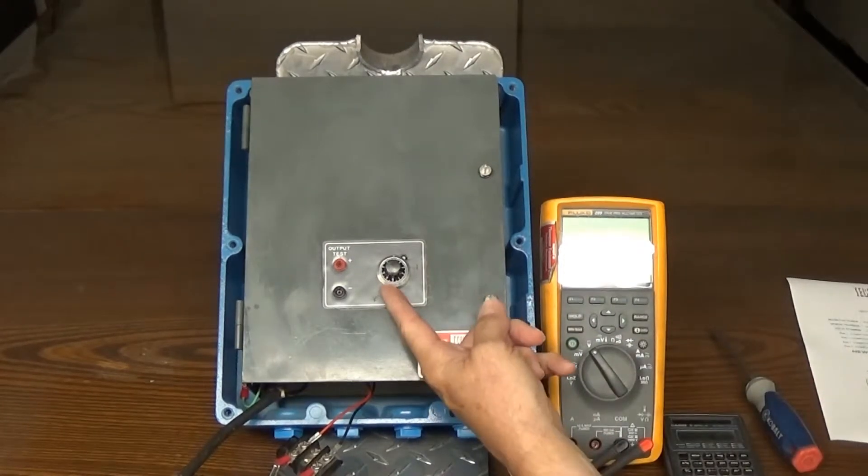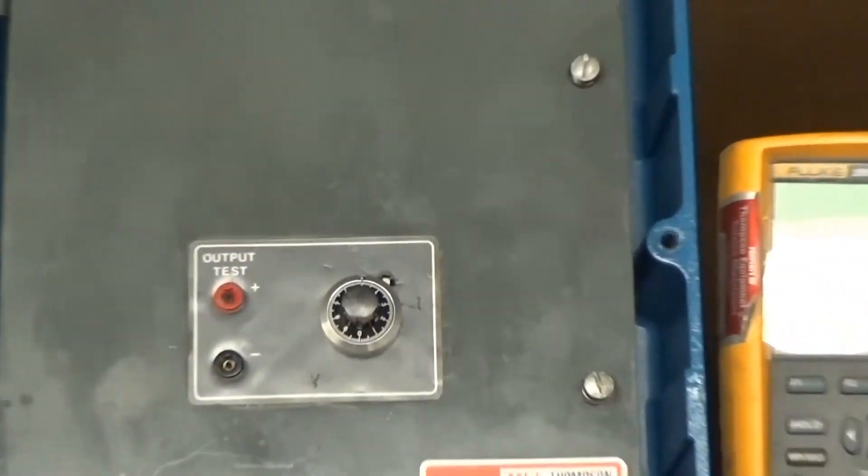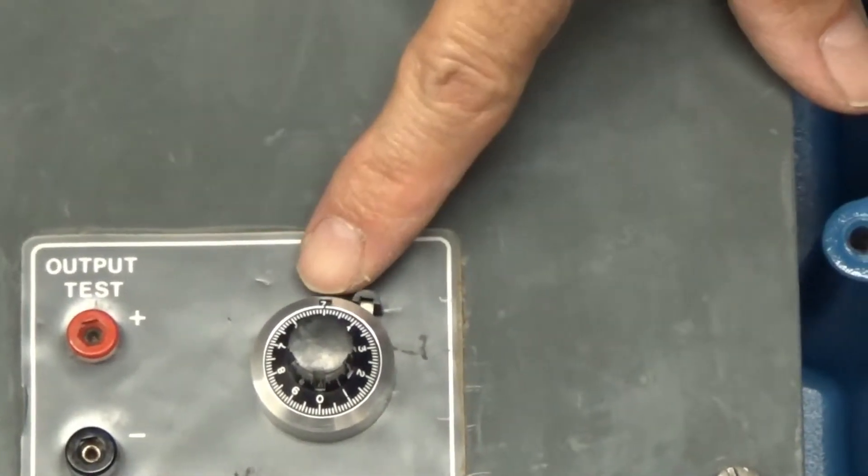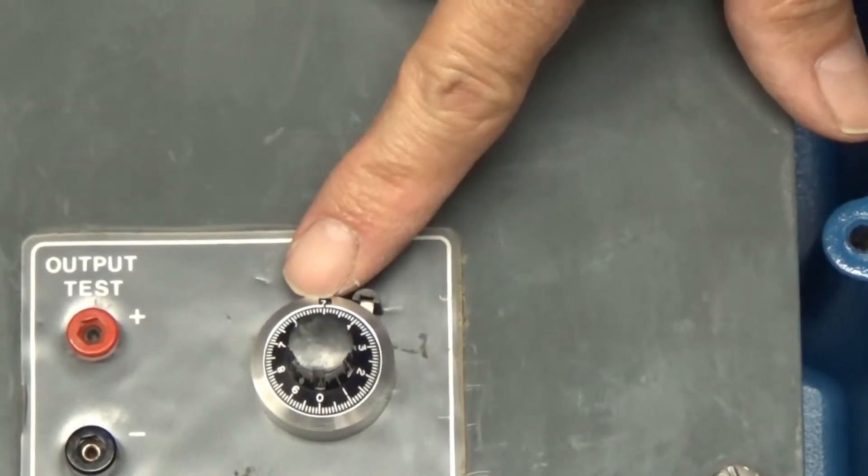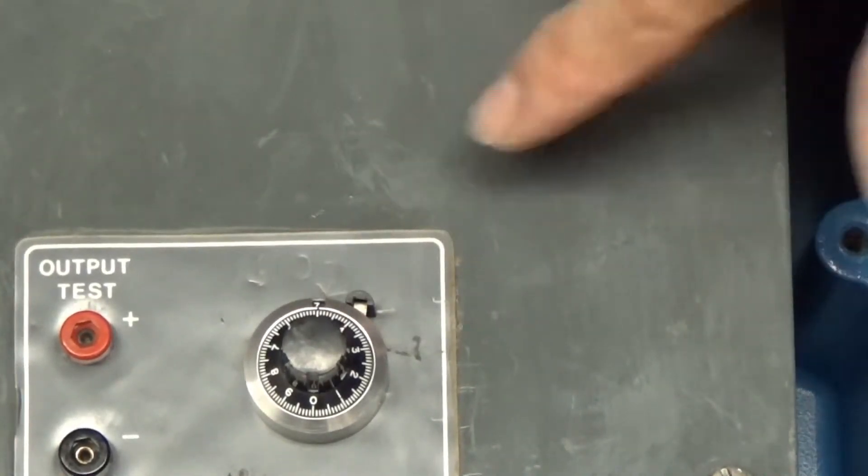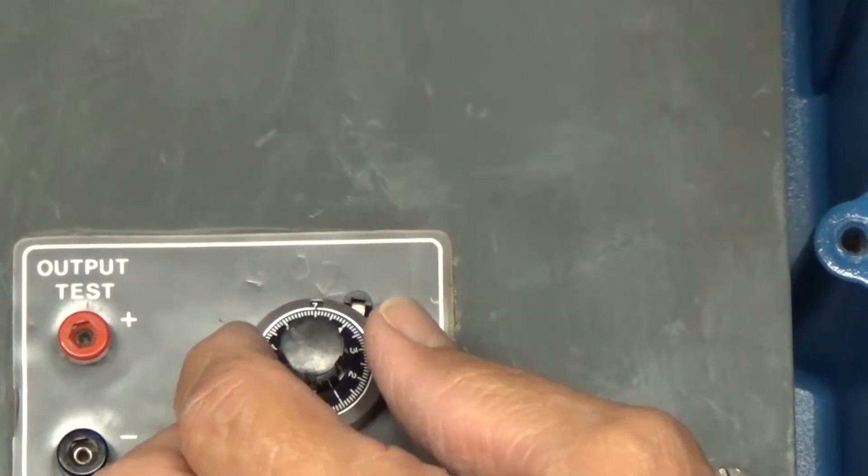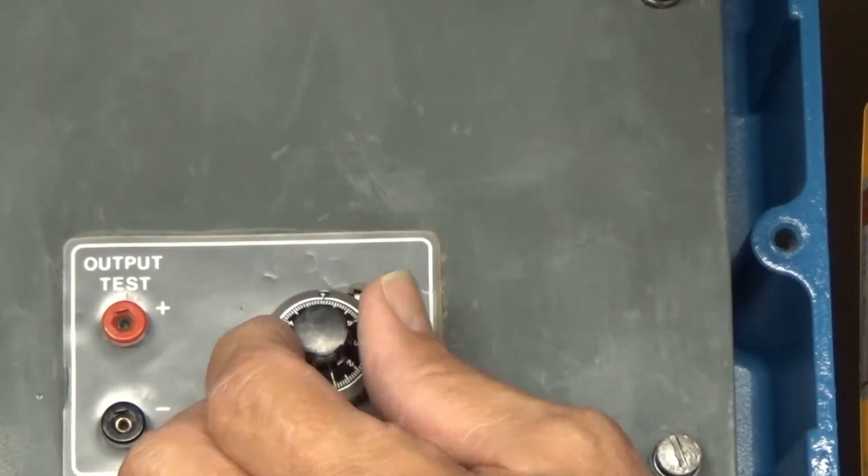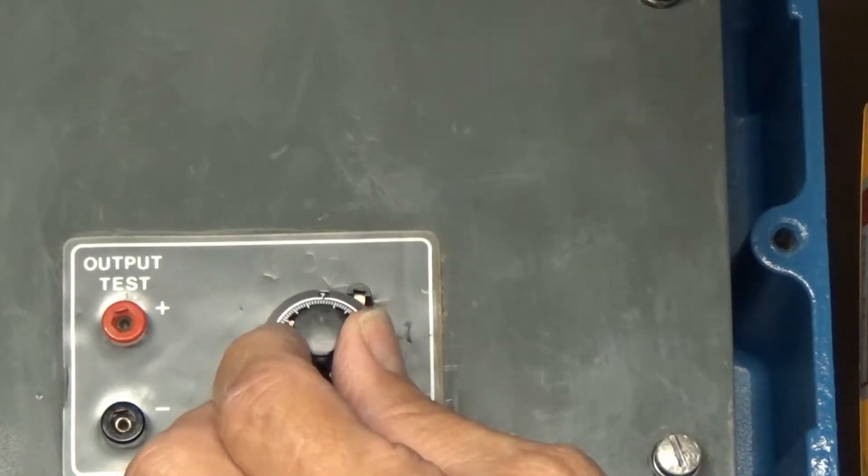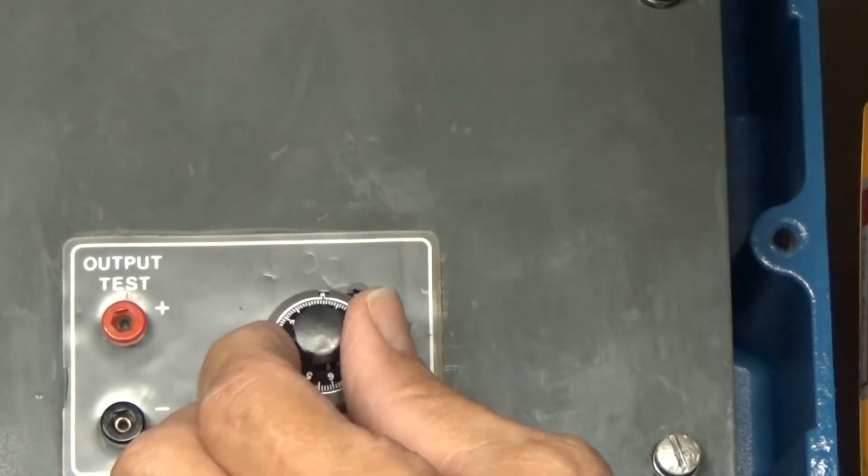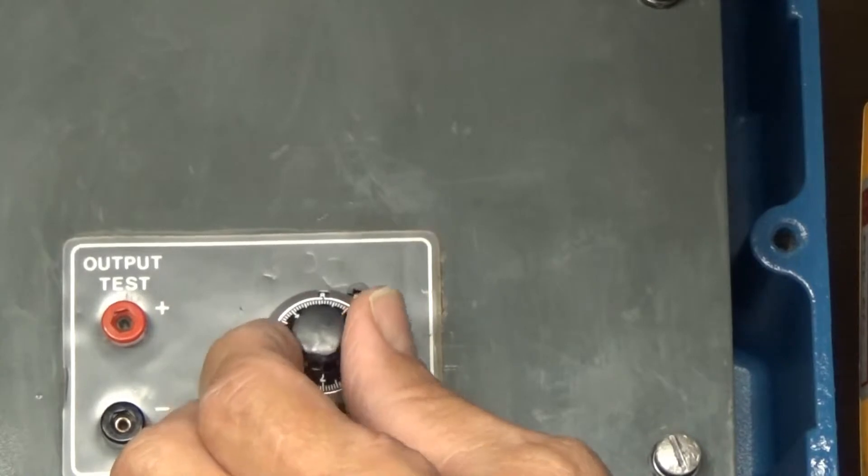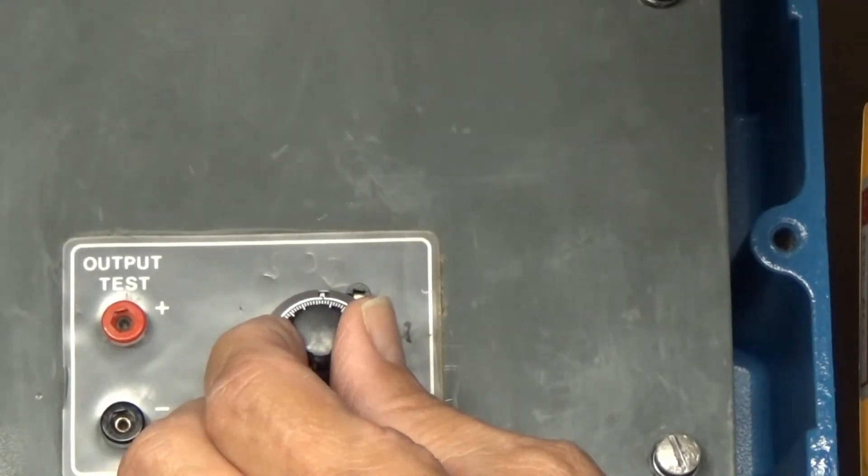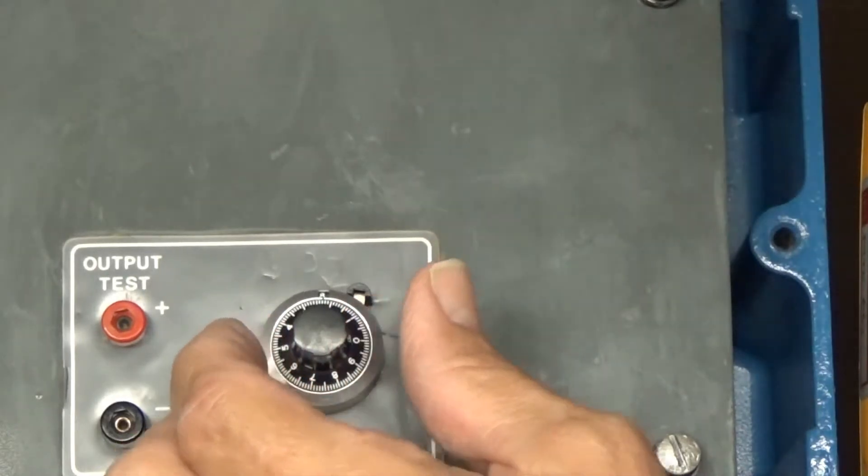And that's the number that we're going to have to dial in to our span potentiometer, which is this device here. There is a number in a window that is your integer part of the number and everything else represents the decimal part. So it's currently set for 7.5. I'm going to turn it up to 8.235. And it's not the easiest thing in the world to see. You may have to zoom in on it. But that is 8.235.